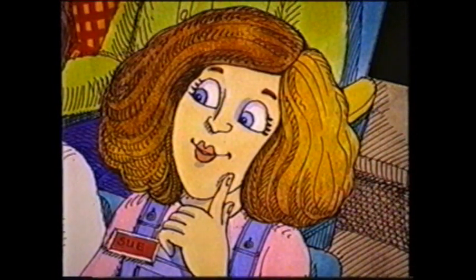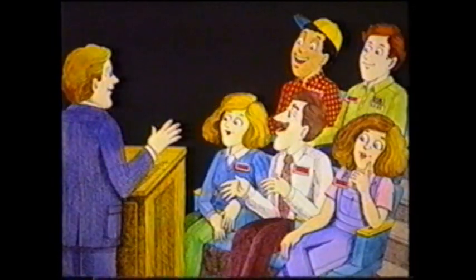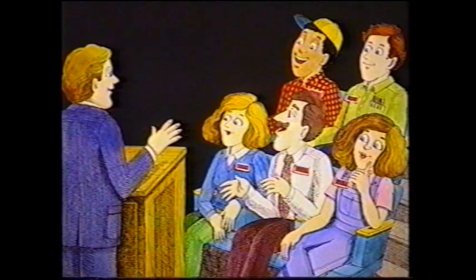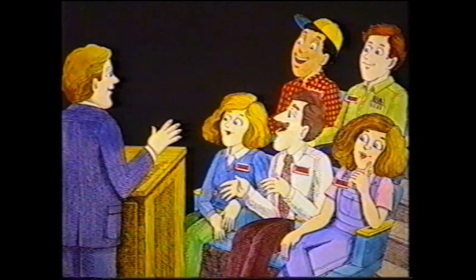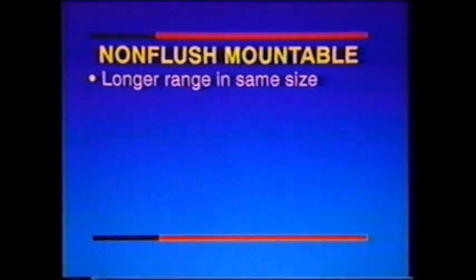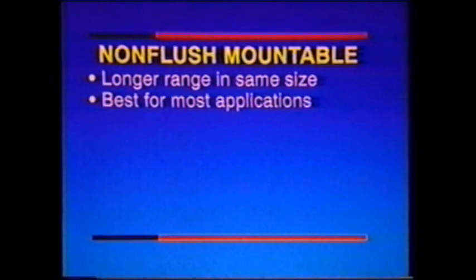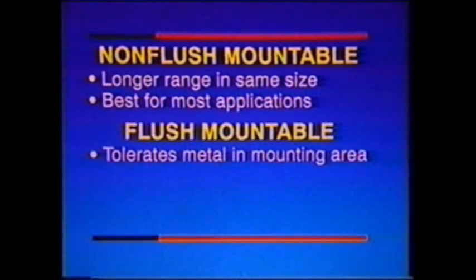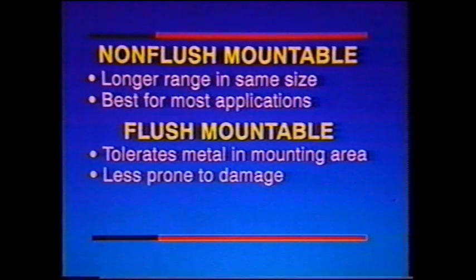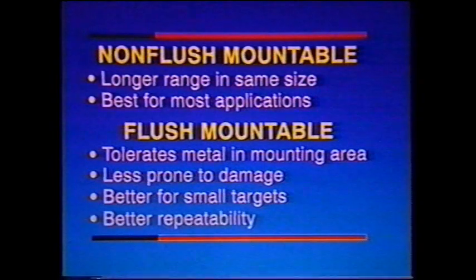Many installations of non-flush switches don't adhere to the metal-free area guidelines because these guidelines are very conservative. In many applications, non-flush switches will work with the metal located closer, but because of pre-damping, they may not give you the same performance in terms of RFI protection, hysteresis, and target detection. Non-flush switches provide the longest range in a given size housing. Flush designs will tolerate metal in the mounting area and are more protected against mechanical damage. Because of their narrower sensing zone, they are also a better choice for small targets and where repeatability is important.